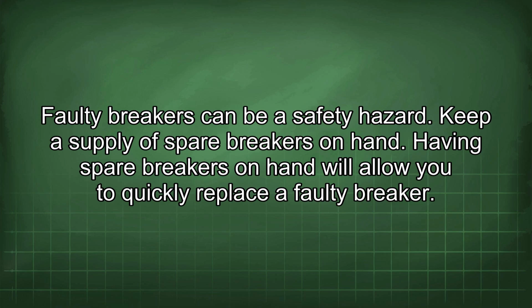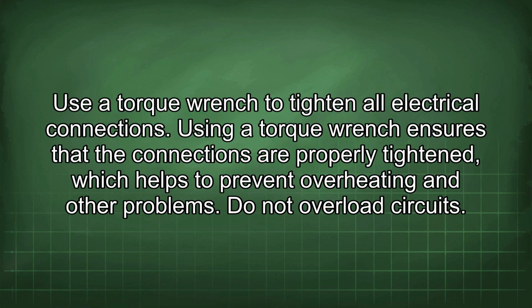Keep a supply of spare breakers on hand. Having spare breakers on hand will allow you to quickly replace a faulty breaker. Use a torque wrench to tighten all electrical connections. Using a torque wrench ensures that the connections are properly tightened, which helps to prevent overheating and other problems.